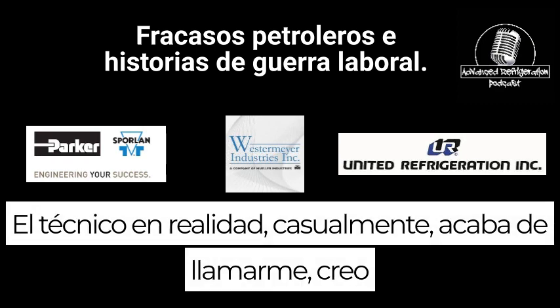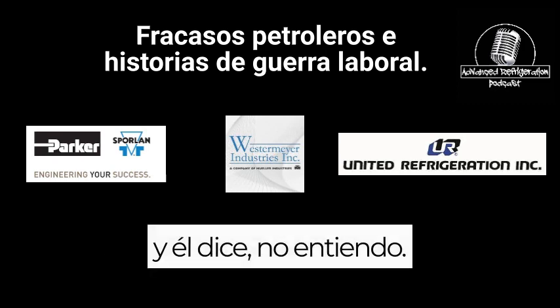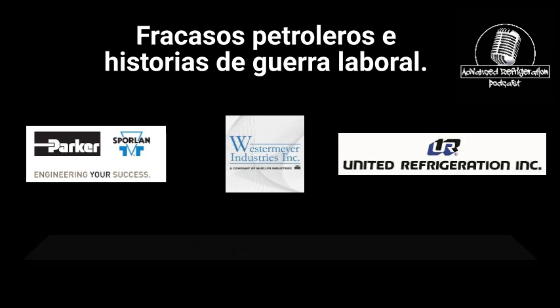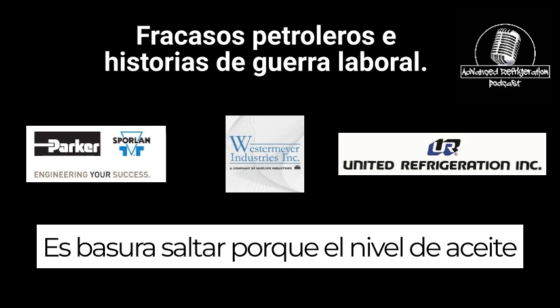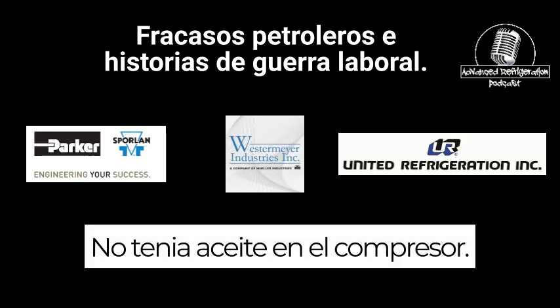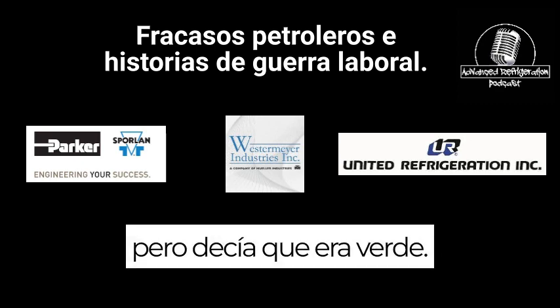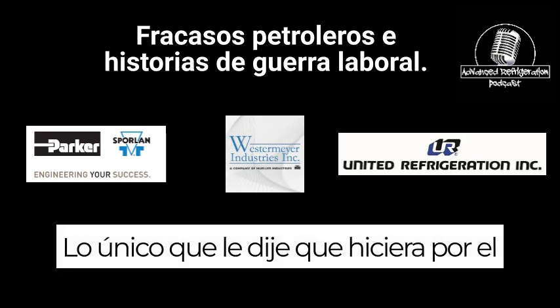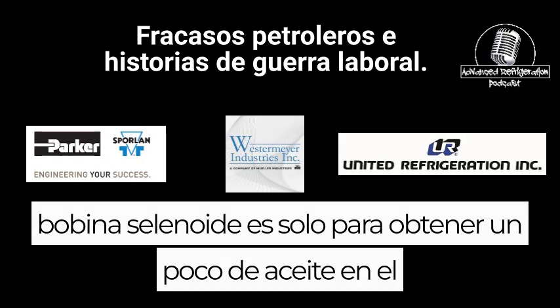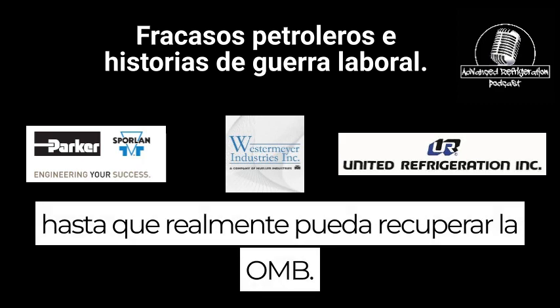A technician actually coincidentally just called me, I think it was yesterday, Domingo. He called me up and he's like, I don't understand. This thing has no oil in it, but it's green. It's garbage. It's junk. Not working. Because the oil level was down, he had no oil in the compressor. Basically, the oil level needed to come up, but it was saying that it was green. The only thing I told him to do in the meantime is throw a magnet on where the solenoid coil is, just to get some oil into the compressor, so he can get the damn thing running until he can actually get the OMB back. You know.